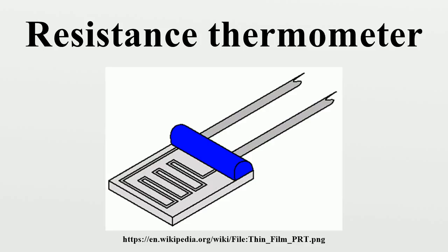applications. Limitations. RTDs in industrial applications are rarely used above 660 degrees Celsius. At temperatures above 660 degrees Celsius it becomes increasingly difficult to prevent the platinum from becoming contaminated by impurities from the metal sheath of the thermometer. This is why laboratory standard thermometers replace the metal sheath with a glass construction.